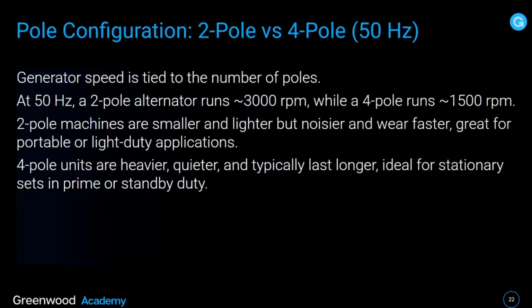Now, generator speed is tied to the number of poles. At 50 hertz, a 2-pole alternator runs at 3,000 RPM, where 4-pole runs at 1,500 RPM. Two-pole machines are smaller and lighter but noisier and wear faster, great for portable or light-duty applications.